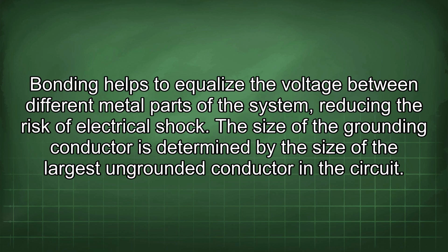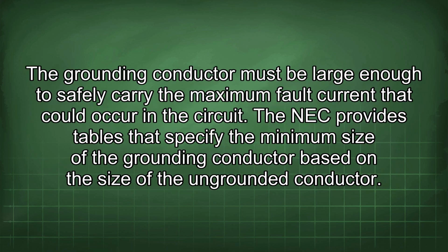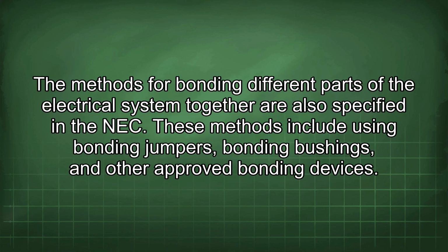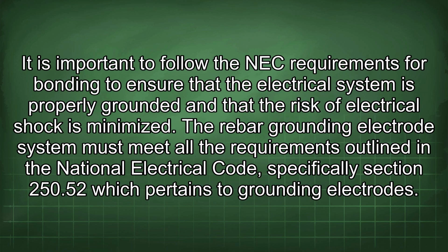The size of the grounding conductor is determined by the size of the largest ungrounded conductor in the circuit. The grounding conductor must be large enough to safely carry the maximum fault current that could occur in the circuit. The NEC provides tables that specify the minimum size of the grounding conductor based on the size of the ungrounded conductor. The methods for bonding different parts of the electrical system together are also specified in the NEC. These methods include using bonding jumpers, bonding bushings, and other approved bonding devices. It is important to follow the NEC requirements for bonding to ensure that the electrical system is properly grounded and that the risk of electrical shock is minimized.